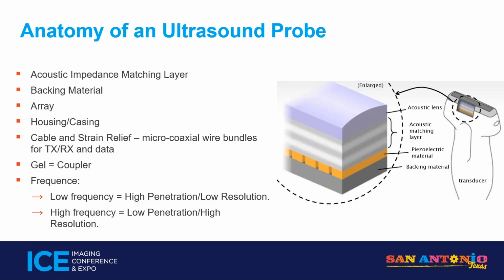So as soon as you see probes that have the lens material missing or damaged, they really should be repaired. And I'd say 90% of probes that have missing or damaged lens can be repaired. There are exceptions where they get dropped and crack the crystals. Okay, that's beyond just a lens repair. But lens repair by itself is a fairly affordable repair compared to the price of the probe. You're talking a few hundred as opposed to thousands to replace the probe. So again, for your facilities, get them repaired as opposed to replaced.